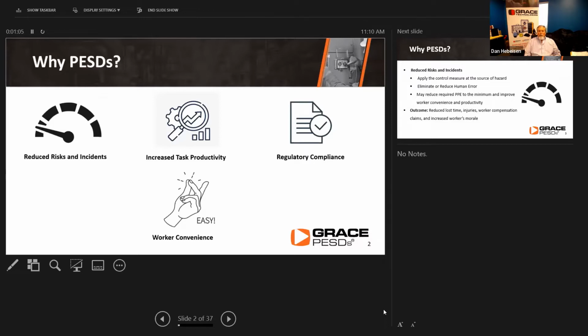But really, what we're talking about is reducing risk and the number of incidences that are taking place. And we know there's a lot of work going on every single day. And unfortunately, as has been reviewed all morning, we're still exposing people to hazardous levels of energy. We're not keeping our one lines up to date. And even if the energy provider were to change a transformer outside of your building, you need to compare that to what you had on your original one lines, because that may have changed when they changed that transformer. Most likely it did.